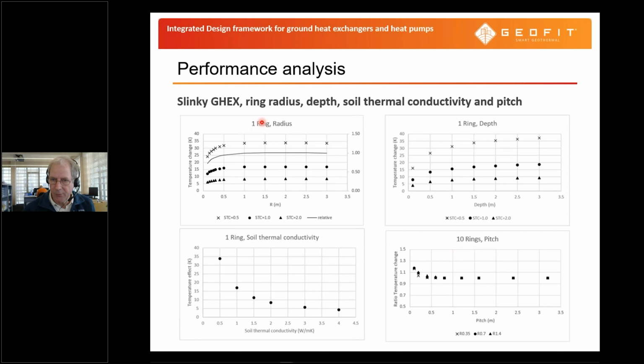And here we've looked at one ring solution. And then if we look at the 10 ring solution, so 10 rings, and then we vary the pitch, the distance between the rings, you can see here that already quite quickly there is no additional effect of larger distances between the rings, but we should have a pitch of slightly bigger than 0.3, 0.4 meters. And actually what we can see as well is that it does not really matter what the actual ring radius is for the effect of the pitch. So it's independent more or less of the actual radius of the ring itself.